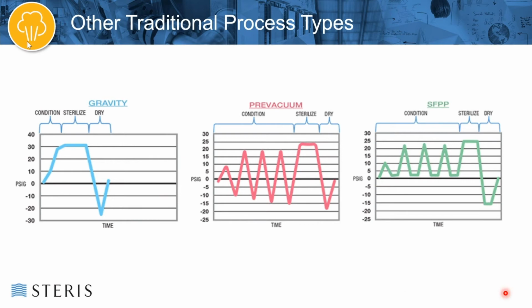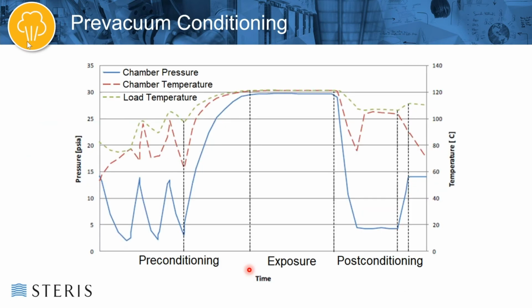So by looking at these slides, the pre-vacuum slide and the SFPP, we know that the previous slide we looked at we can call a pre-vacuum because we can see these pulses down here. What's interesting is that this is PSI-A, so atmospheric is going to be just slightly below 15 PSI-A. So you can see that all of these pulses are subatmospheric.